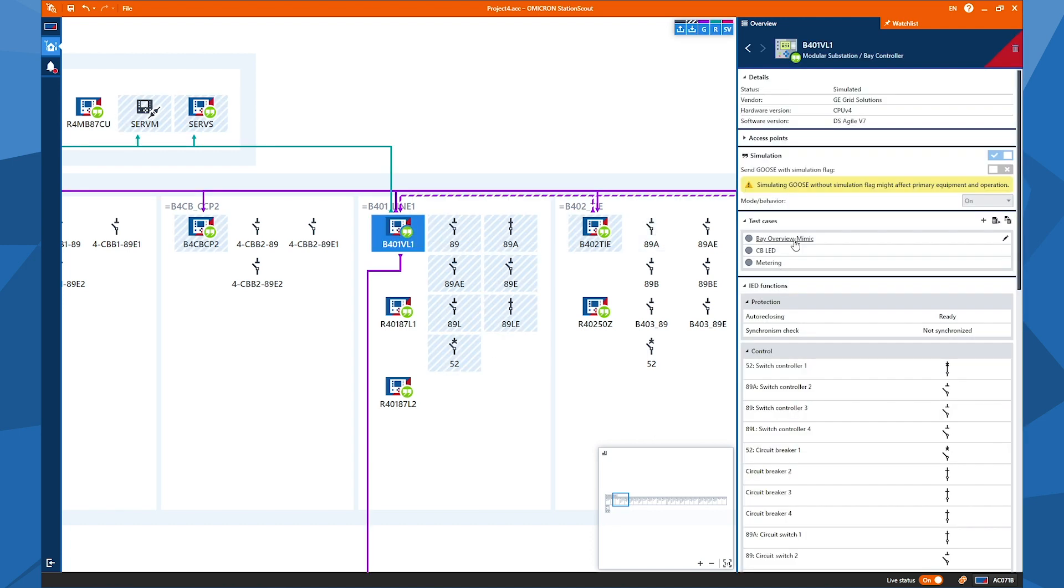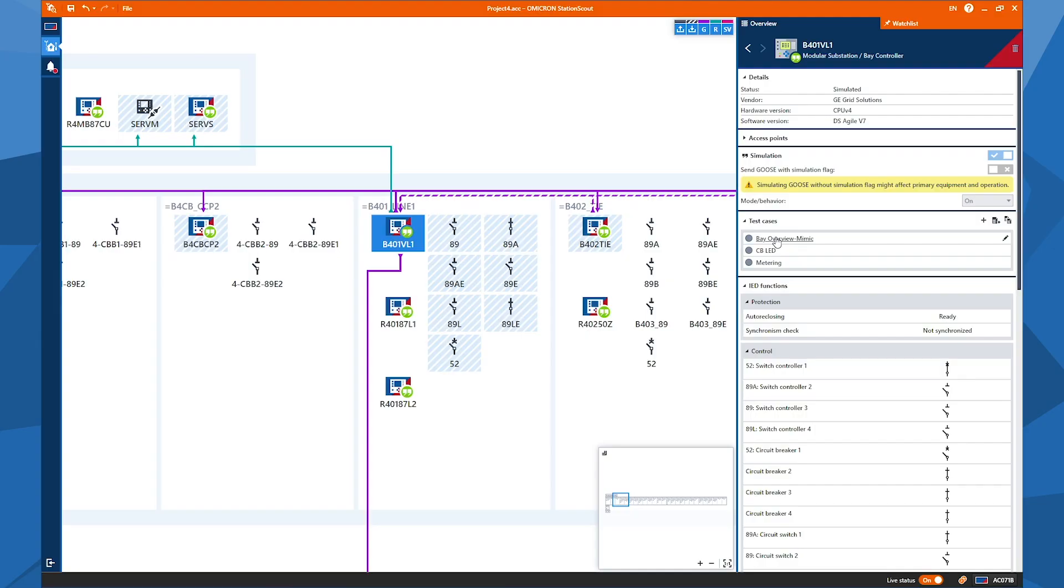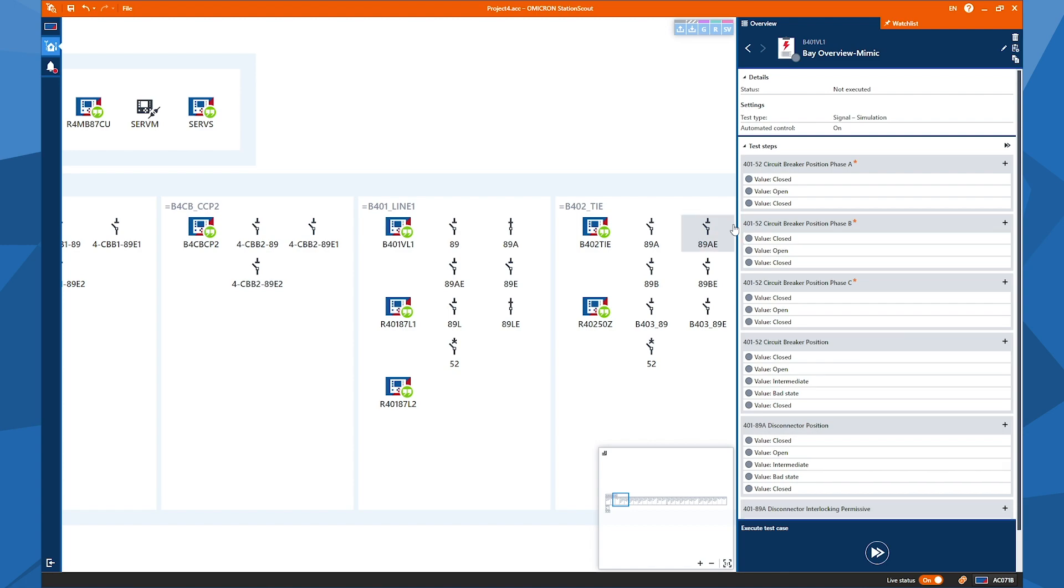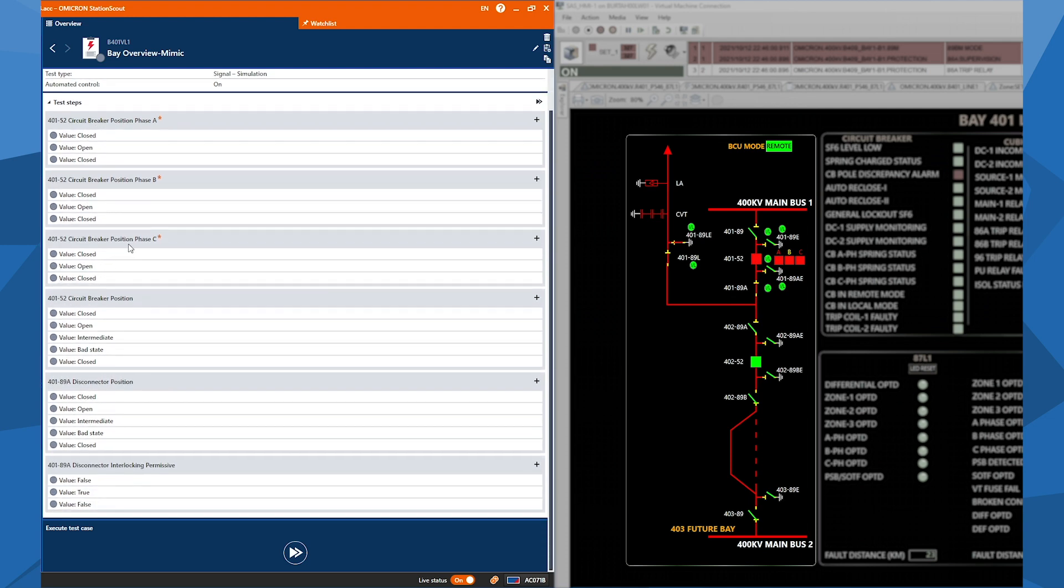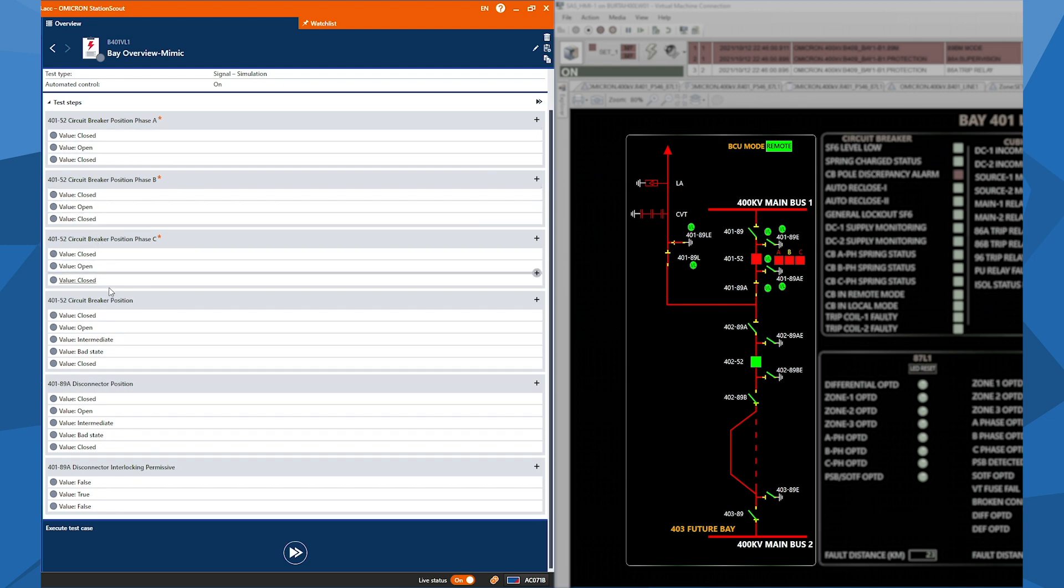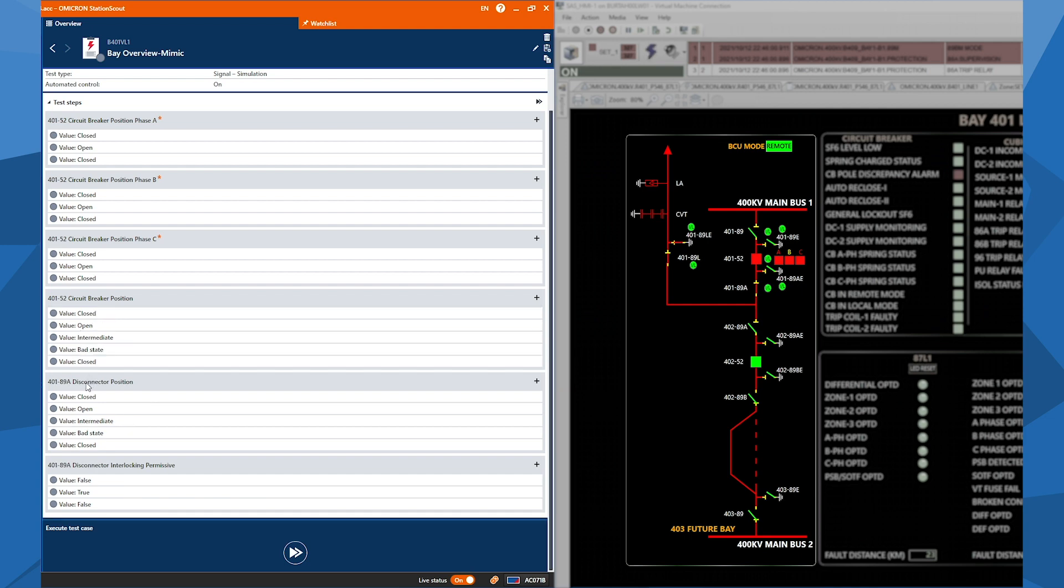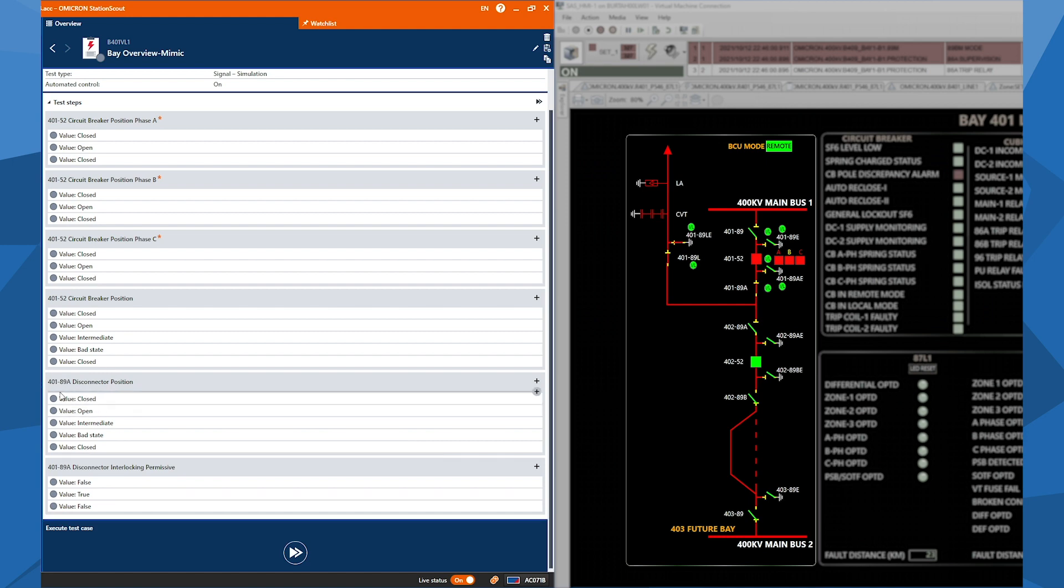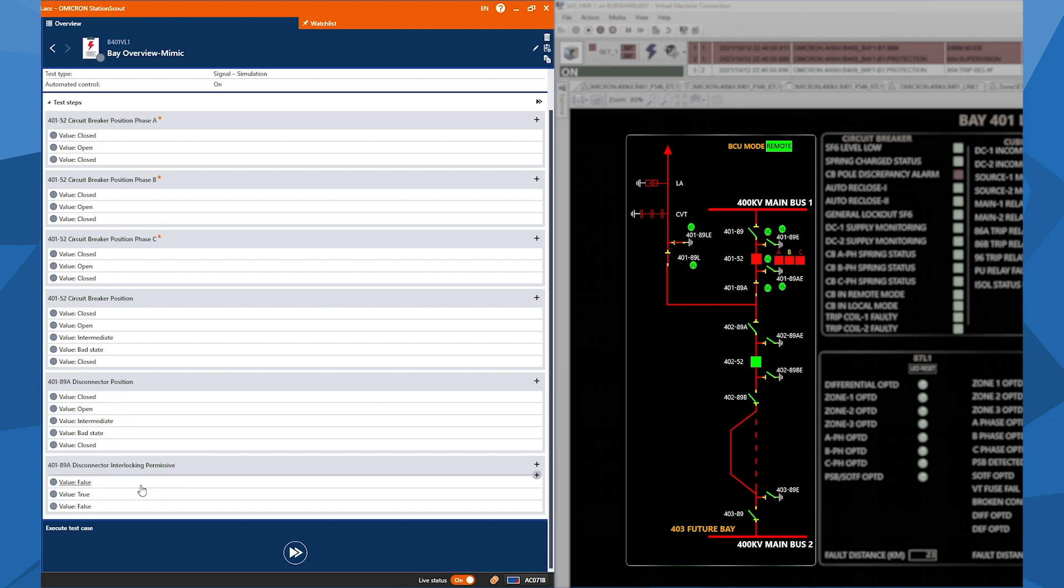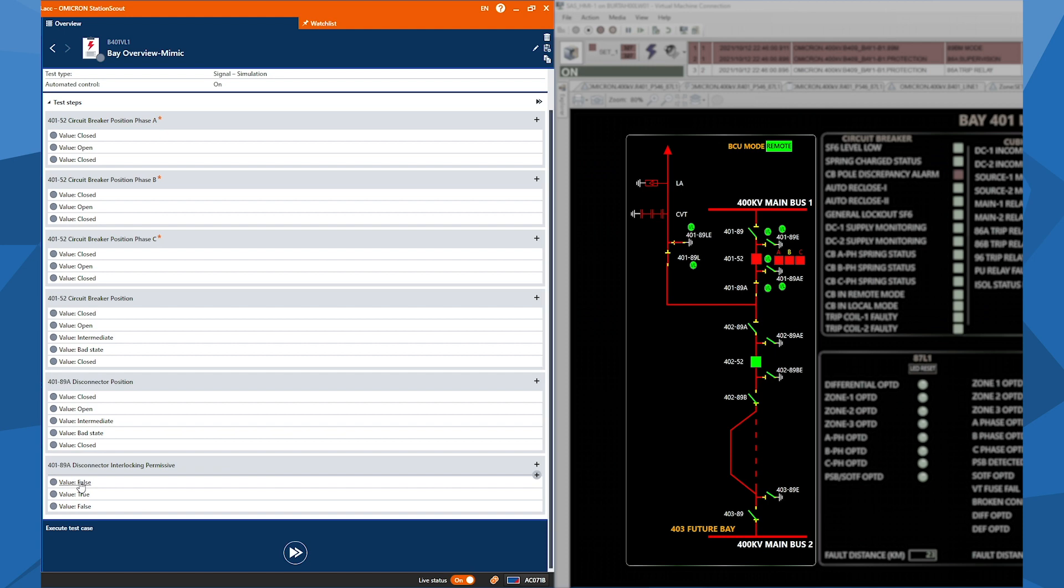So it's the mimic diagram which will be tested now. So this is this one, and I click on this test, and let's have a look on the test case what we prepared here. So I see that it's the circuit breaker positions, the single-phase ones. It has a closed-open-closed cycle, and the circuit breaker, the three-phase position, it has all the possible statuses. And you can have also delayed some of them or add the ones that you want to test. It's all possible, as we mentioned before. And 89A, which is the disconnector here, you can see it, 89A is closed here. And also we have some icons that represents the interlocking release signals, and with these icons we can also test its single point status symbols.